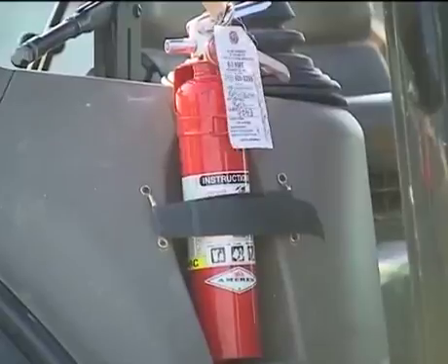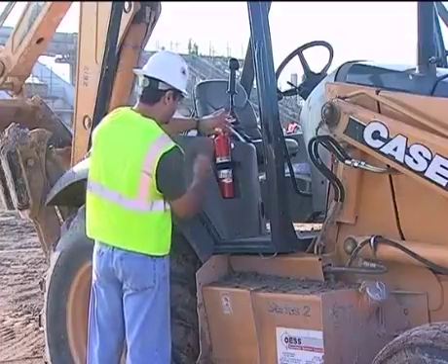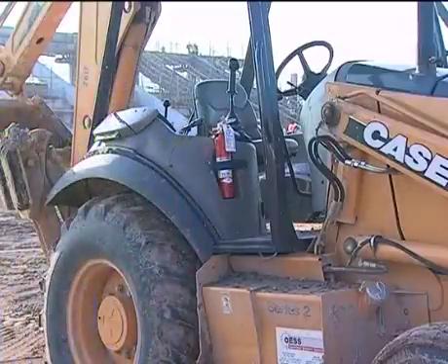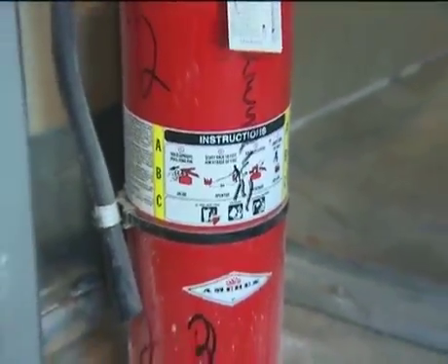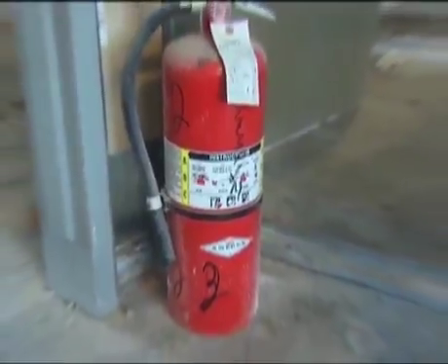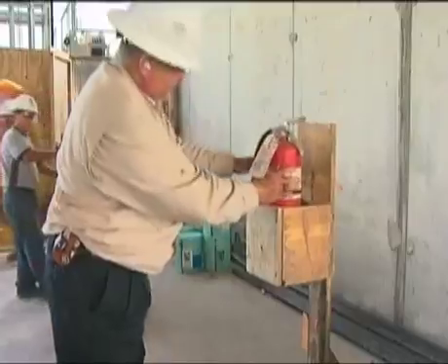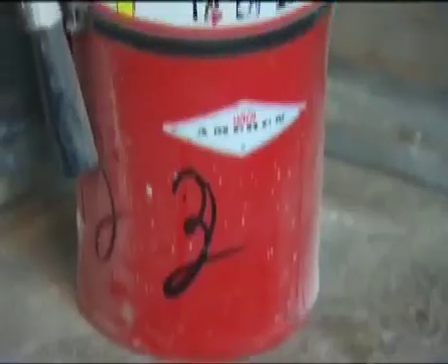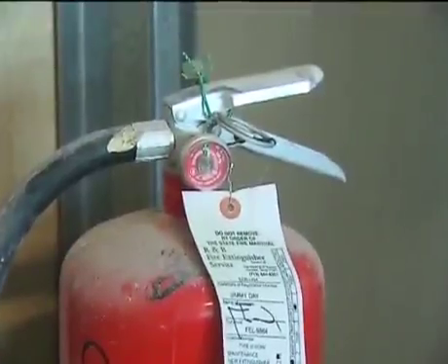Your company should perform monthly inspections on its fire extinguishers. Be sure that all extinguishers are in the proper areas and are easily visible and accessible. It is important that you or someone within your workplace verifies that all extinguishers indicate the correct pressure for proper use. An annual professional inspection certified by your state's fire marshal needs to be completed. During this annual inspection, any maintenance needs to be completed according to the type and age of the extinguishers your company uses.